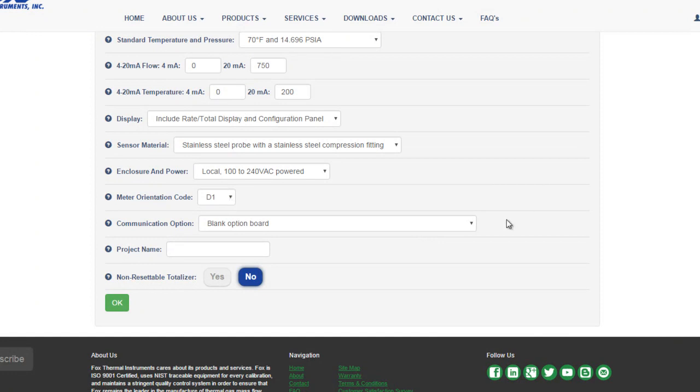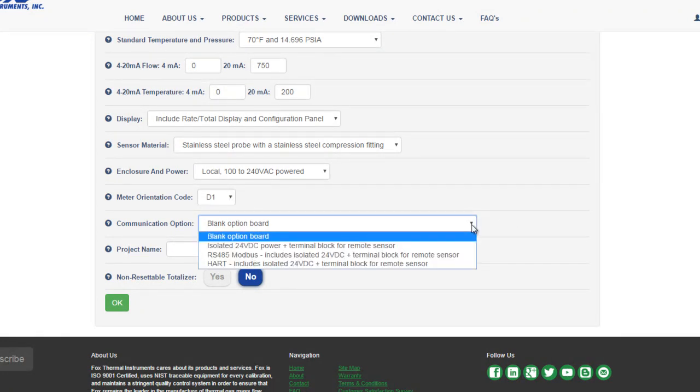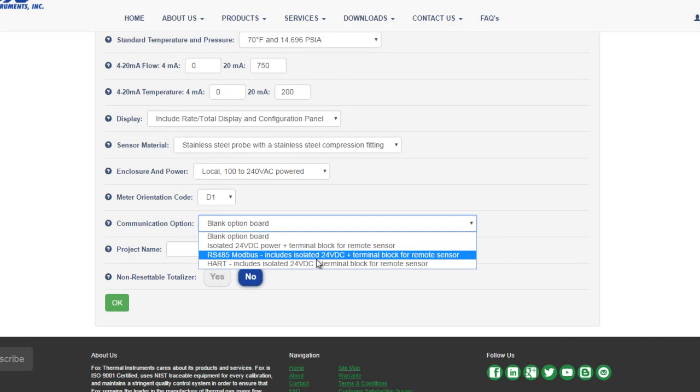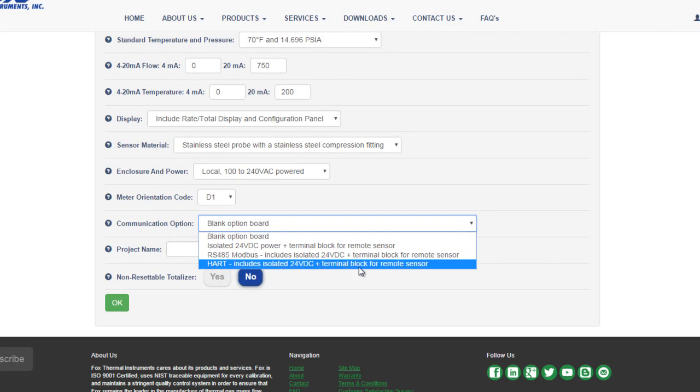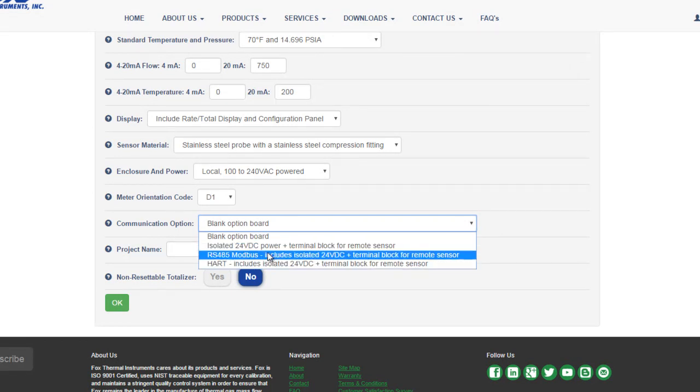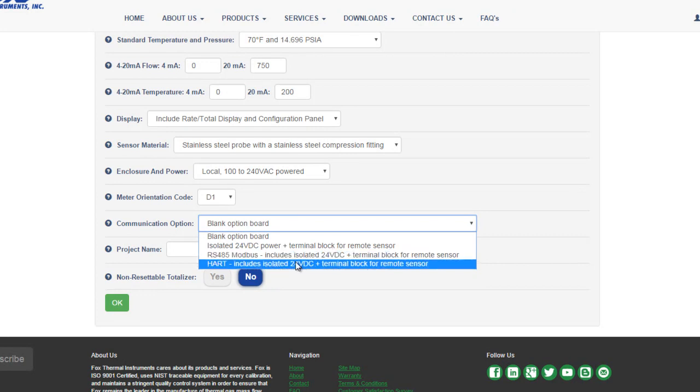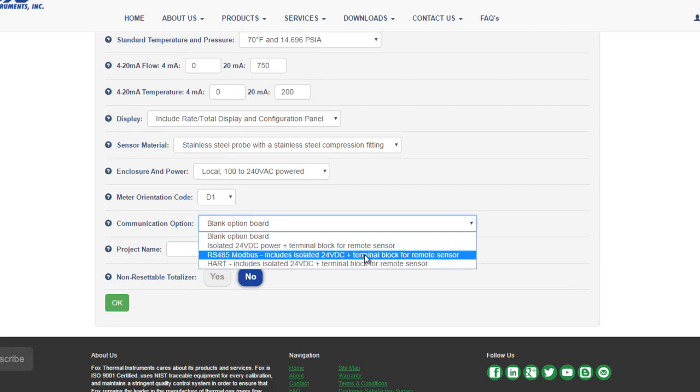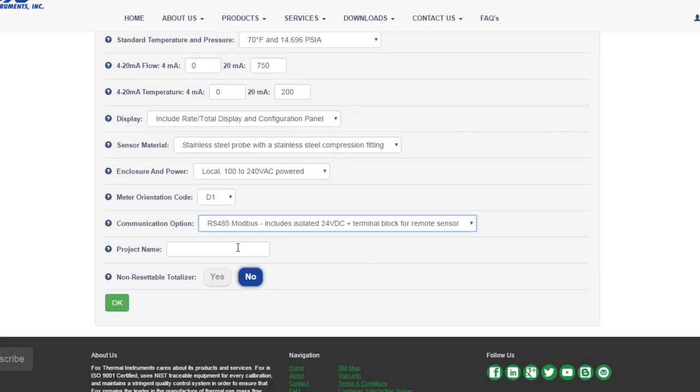Next we get to choose between optional communication outputs. The first option is a blank board. If you have a remote display in your application, you must choose between one of the other three options. The standard, terminal block for the remote sensor, a Modbus output, which includes the terminal block for remote sensor, or a HART output, which includes the terminal block for remote sensor. Let's choose Modbus this time. Again, you can enter a project name. We'll skip that this time. And finally you have the option of a non-resettable totalizer.